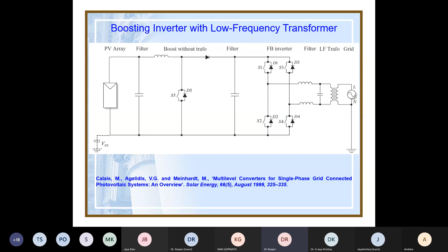So what is the grid requirement of PV? First, the voltage harmonic level - maximum total harmonic distortion (THD) is 8%. And voltage unbalance for a three-phase inverter, maximum unbalance is 3%. More than that, it will draw a completely different large current from the inverter, causing overcurrent that may exceed the inverter's rating. So it should be within 3%.